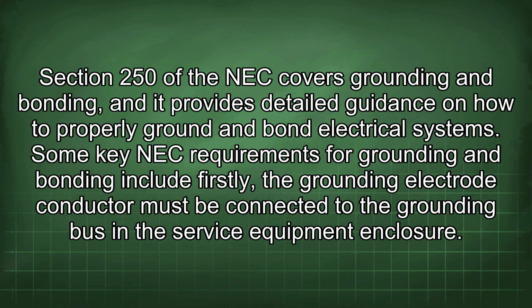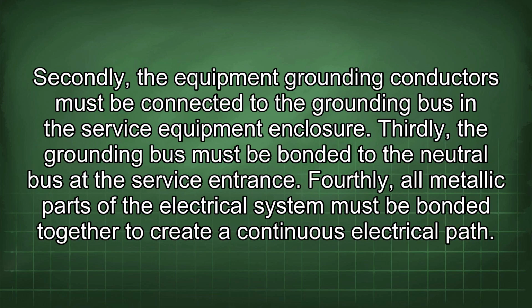Section 250 of the NEC covers grounding and bonding, and it provides detailed guidance on how to properly ground and bond electrical systems. Some key NEC requirements for grounding and bonding include: firstly, the grounding electrode conductor must be connected to the grounding bus in the service equipment enclosure. Secondly, the equipment grounding conductors must be connected to the grounding bus in the service equipment enclosure. Thirdly, the grounding bus must be bonded to the neutral bus at the service entrance. Fourthly, all metallic parts of the electrical system must be bonded together to create a continuous electrical path.